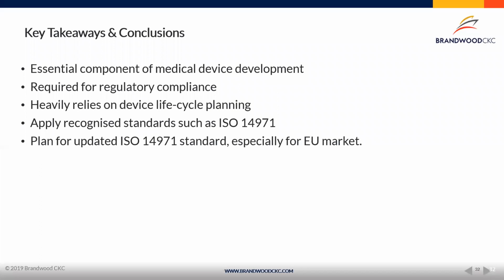Applying the recognized standard 14971 or any of those other standards we've mentioned in the slides. 14971 is the Bible, so to speak, when it comes to risk management for medical devices. But we have to apply the other standards as appropriate. In some standard cases, it actually just goes back to 14971.